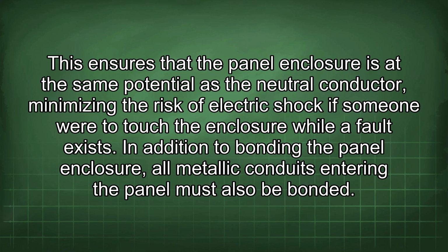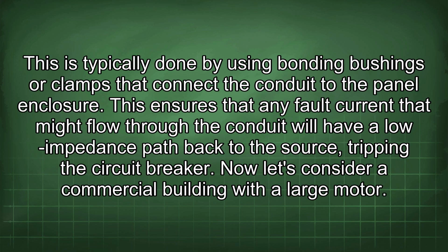In addition to bonding the panel enclosure, all metallic conduits entering the panel must also be bonded. This is typically done by using bonding bushings or clamps that connect the conduit to the panel enclosure. This ensures that any fault current that might flow through the conduit will have a low impedance path back to the source, tripping the circuit breaker.